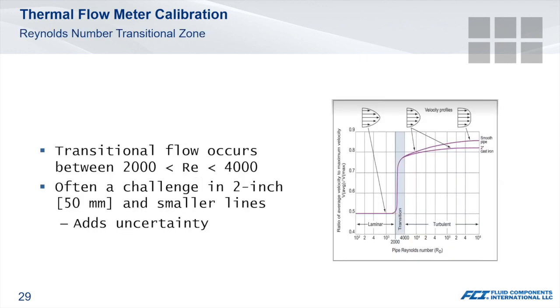Most flow measurement technologies have issues when a gas flow transitions between laminar and turbulent flow. For thermal meters, this most often can be seen in smaller line sizes. Since the flow is neither laminar nor turbulent in this region, there are calibration challenges associated with the randomness of the velocity profile.